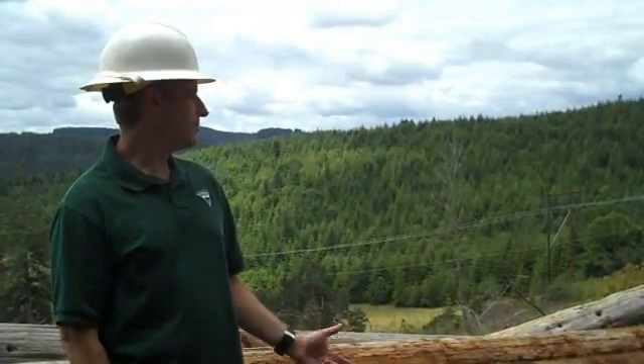Wood, being a natural material, tends to degrade over time, and our goal is to keep the system safe and reliable by replacing the bad poles before they fail. These are some of our poles that have been pulled out — there's a project going on to replace these poles. Over time, the lines will degrade to the point where they get beyond what our crews can take care of, and so they become a good project to contract out, taking advantage of the size of the project.